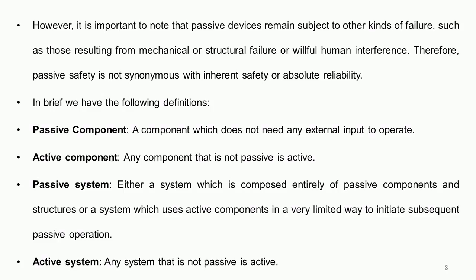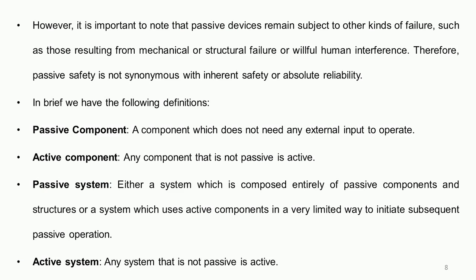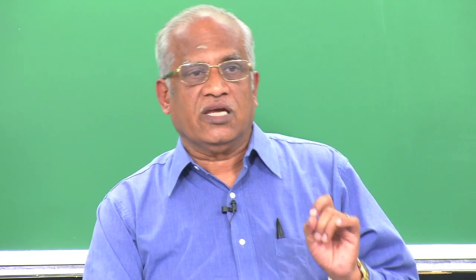For a motor-driven pump for cooling, you can check it anytime by putting on the power supply to see whether the pump is running and supplying water. But for a passive system, how do you check? There is no manual switch. Passive system is not synonymous with either inherent safety or absolute reliability. There is a feeling among many young designers that if you make a system passively safe, it is as good as inherently safe or will operate with high reliability — but that is not the case.